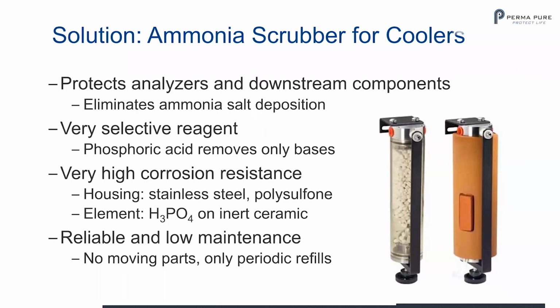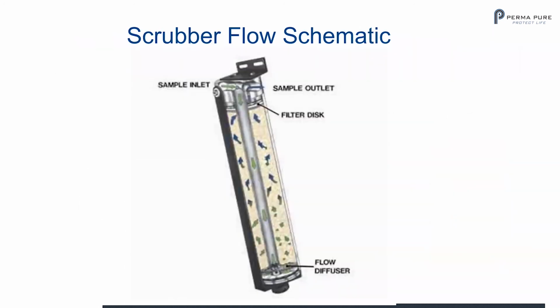So the solution is to add ammonia scrubbers for coolers. This protects analyzers and downstream components by eliminating ammonia salt deposition. Like I mentioned before, we have phosphoric acid on the ceramic saddles that capture the ammonia, and we have a heated blanket that keeps that operating at a high temperature. And here's your scrubber flow schematic. We have your inlet and outlet on the top, and your sample flows down and then up through the saddles and phosphoric acid, where it comes out with the ammonia removed.